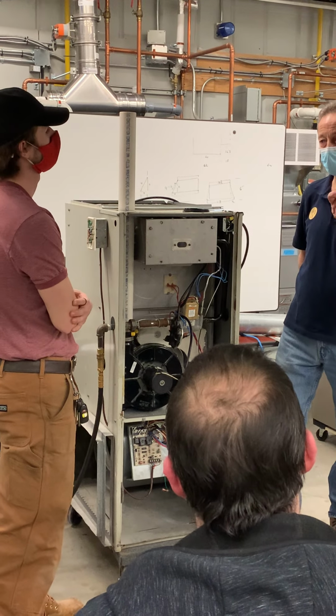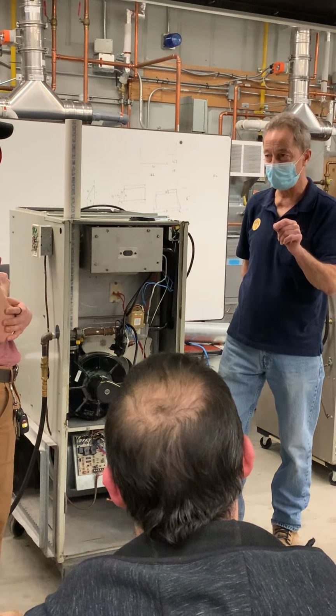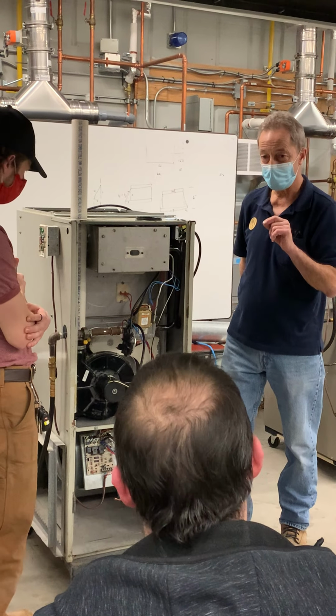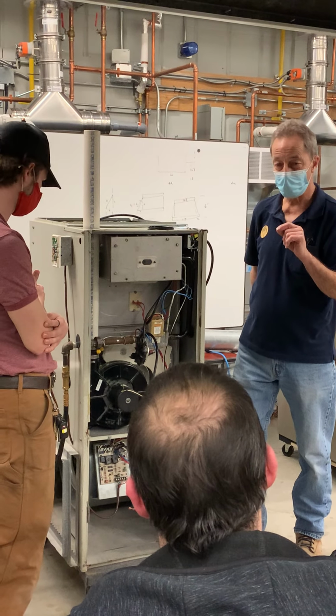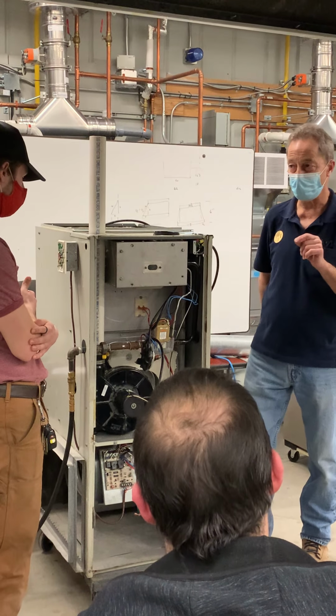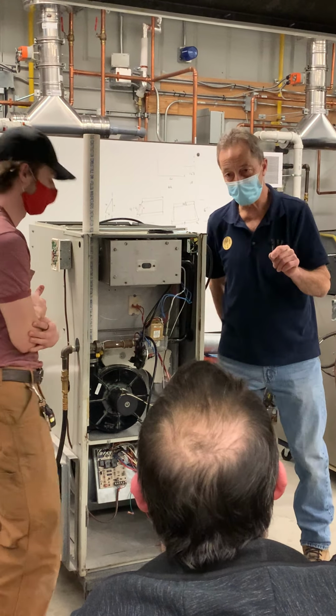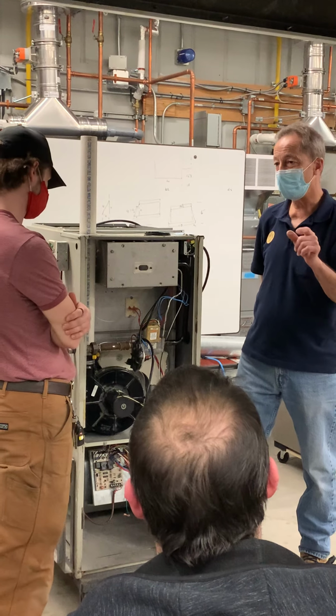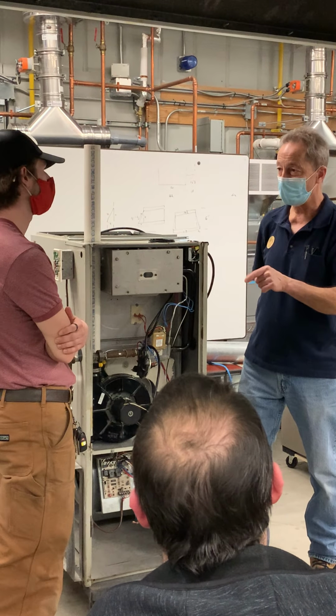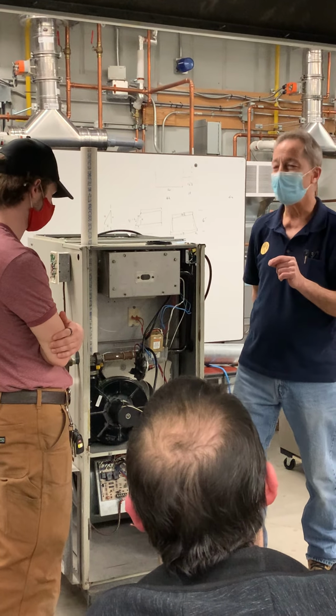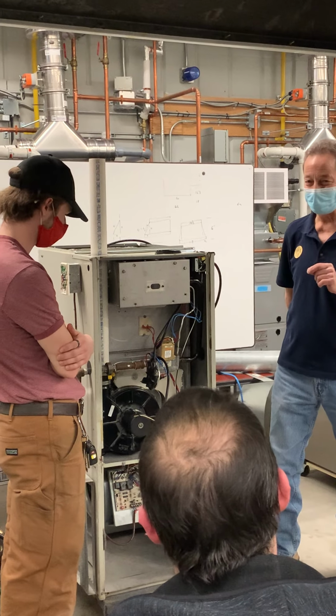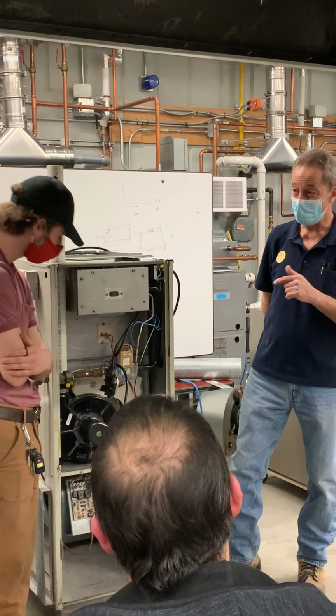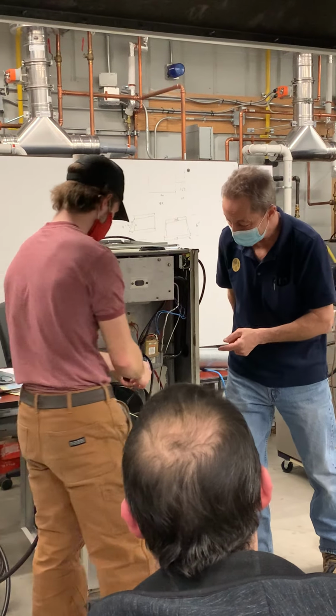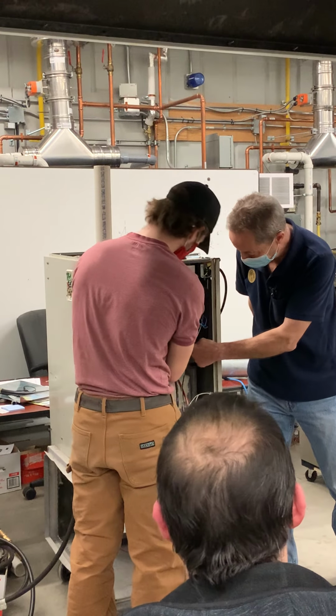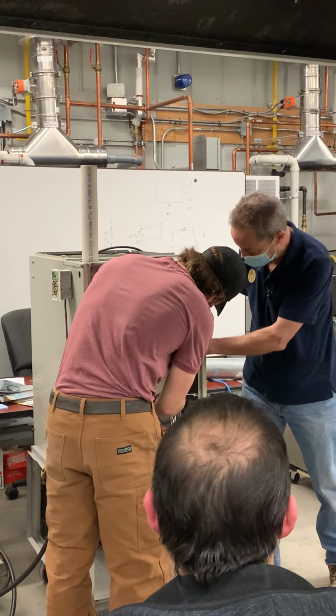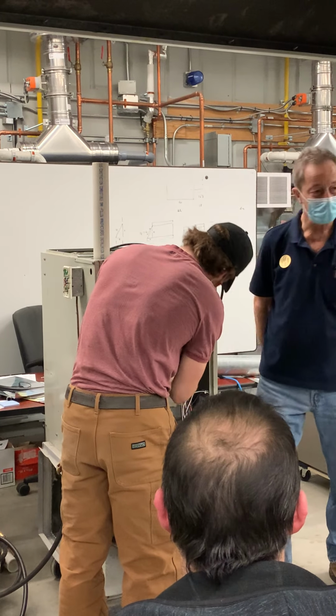When the pressure switch closes, where does the signal from the closed pressure switch go? Down to the board. No, wait, I haven't finished asking the question yet. When the pressure switch closes, where does the signal from the pressure switch go? And don't say to the board below. To the gas valve. Thank you, it goes to the gas valve. Okay? Follow it. So like these wires here. Yeah, you can follow it. Blue ones. And one of the blue ones loops and comes up here to this one. In here, yeah.